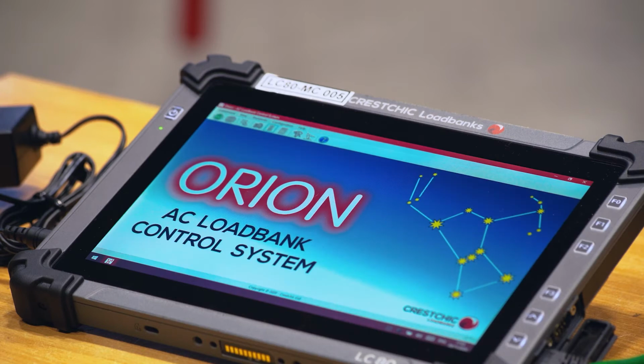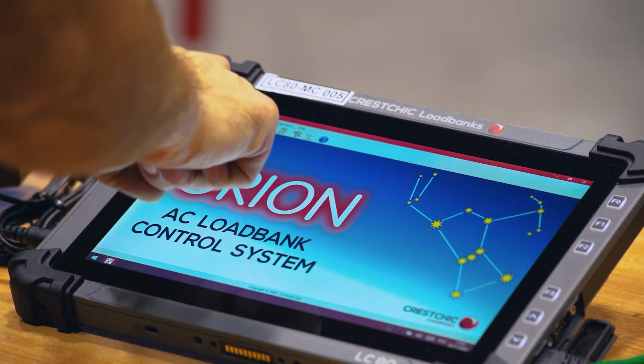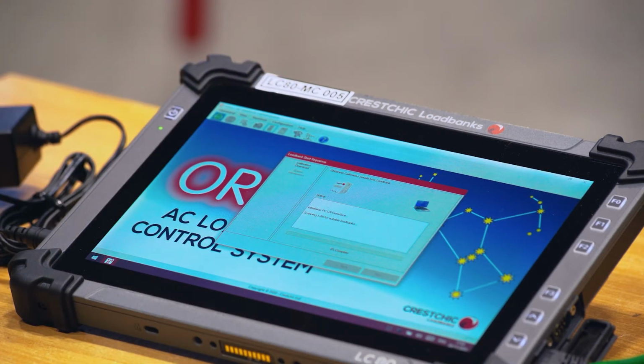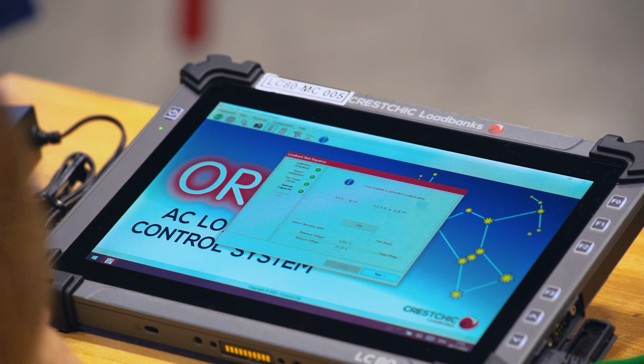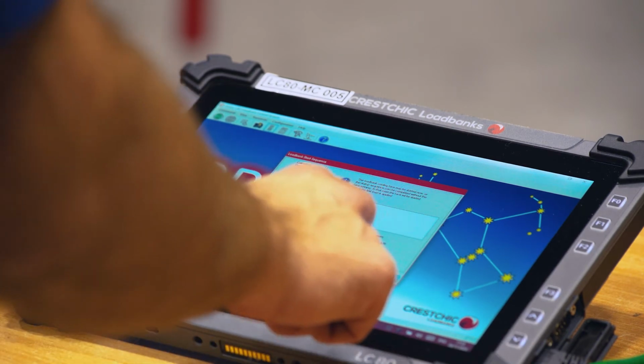In the Orion software, Press and Go will gather information from the load bank and show the load bank specification and settings. Once the screen where the fans can be started is reached, start the fans and check these are running in the correct direction.